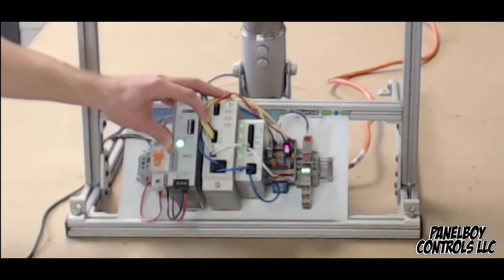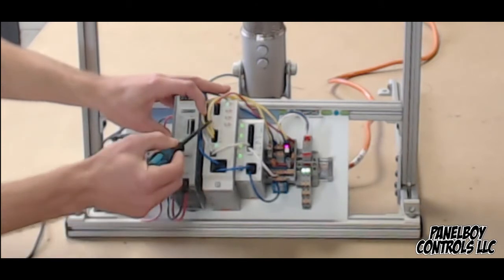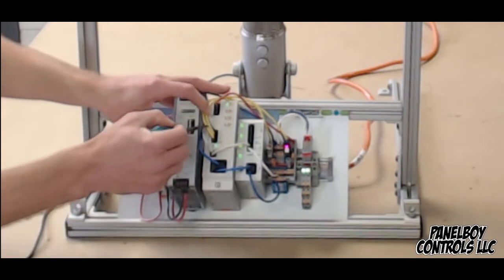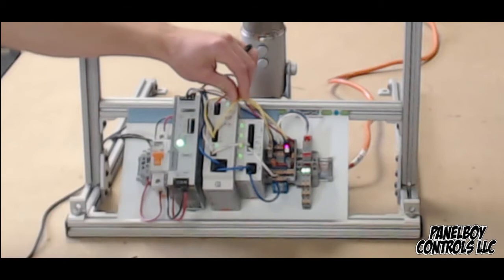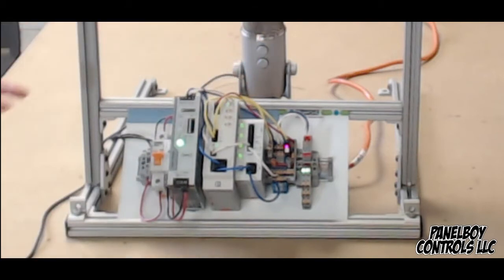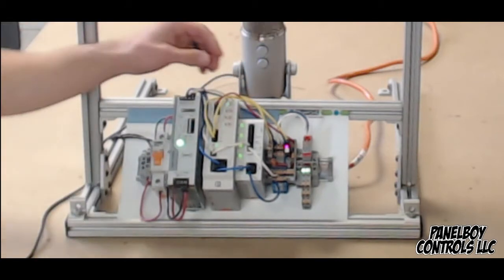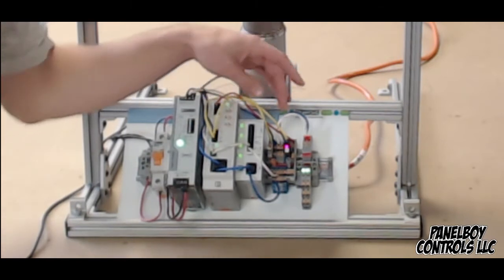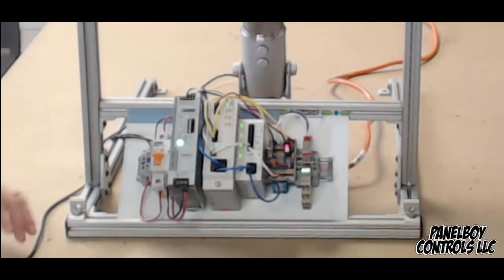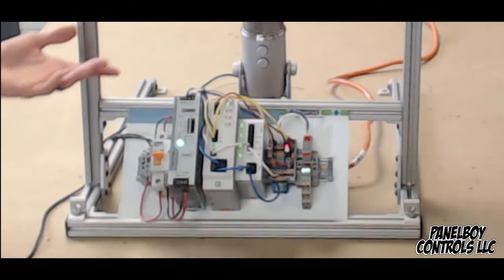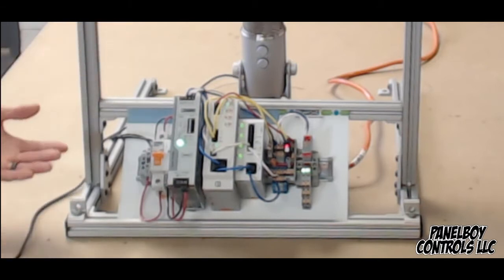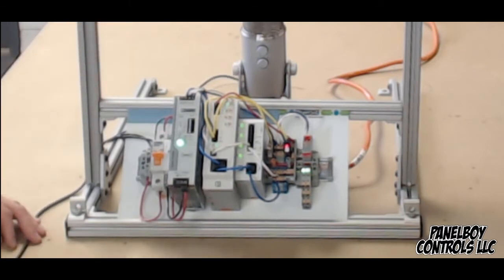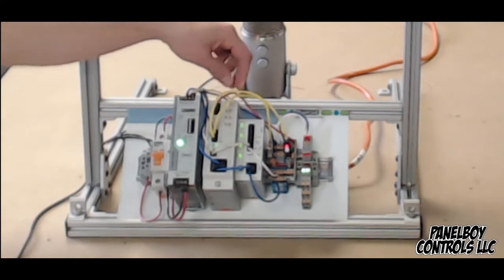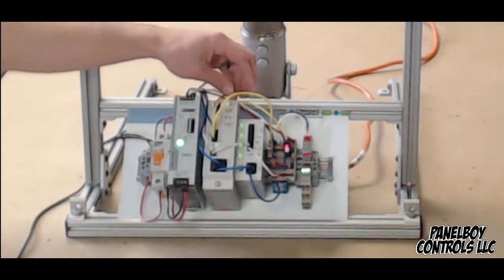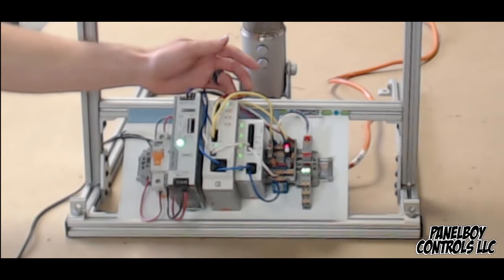I've got a dry contact for letting me know if something is true, which could be tied back to a PLC. I feed this 24 volts and have my diagnostic wire. In this case it's not going to a PLC since I didn't have room on the board, so instead I tied it to a little LED indication, really a blown fuse indicator, though I don't have a fuse in there, just for demonstration purposes. I've also got a reset, and I'll show you how you can reset this either remotely or locally.